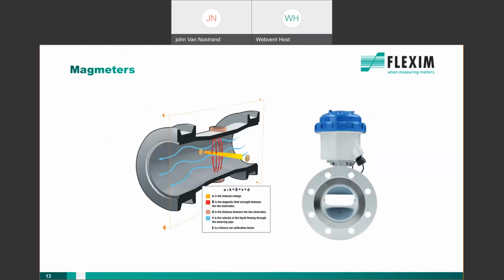So with a magmeter, it's a little bit different. A magmeter works on the principle of Faraday's law, and that means that when a conductive liquid flows through the magnetic field, which is created in the spool, voltage is induced, and that voltage is proportional to the velocity of the flow. So there are two electrodes that are mounted on opposite sides inside of the flow process. They protrude into the flow process. And these two electrodes are connected to an electronic input circuit, which processes the signal and in turn feeds it to a microprocessor. The microprocessor then calculates the volumetric flow.